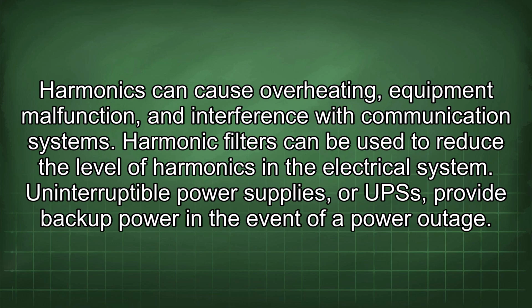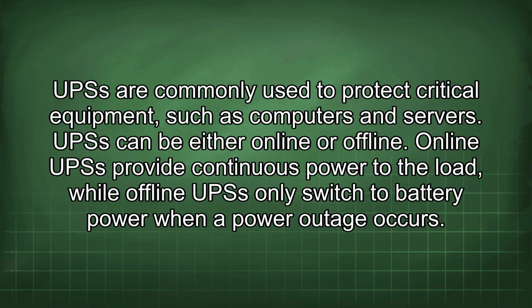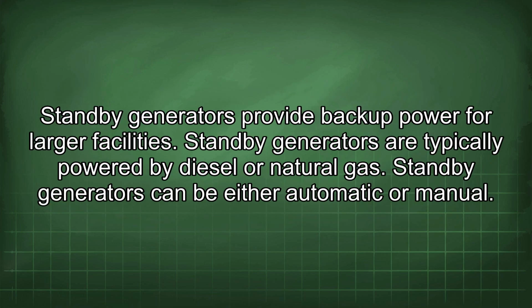Uninterruptible power supplies, or UPSs, provide backup power in the event of a power outage. UPSs are commonly used to protect critical equipment, such as computers and servers. UPSs can be either online or offline. Online UPSs provide continuous power to the load, while offline UPSs only switch to battery power when a power outage occurs.